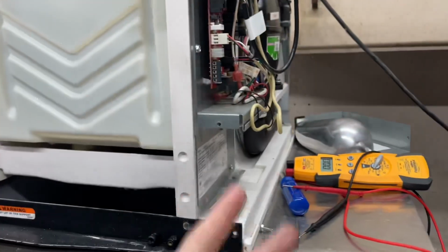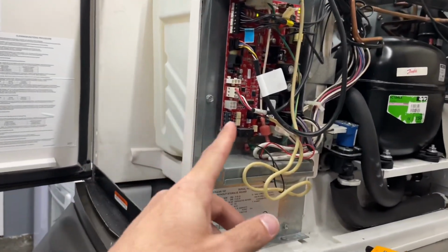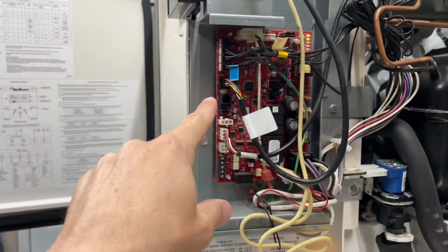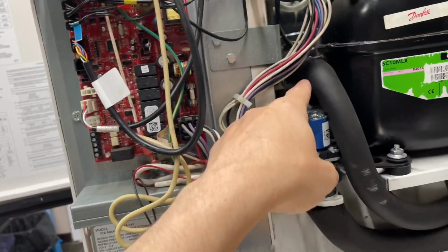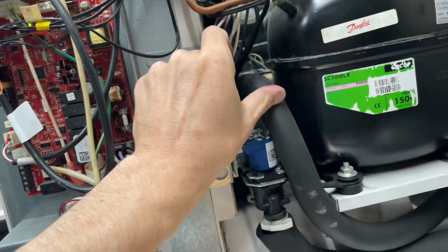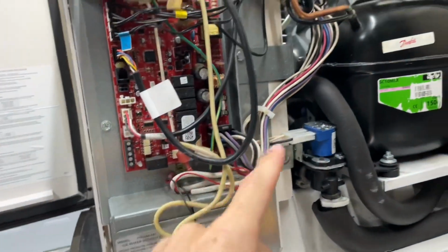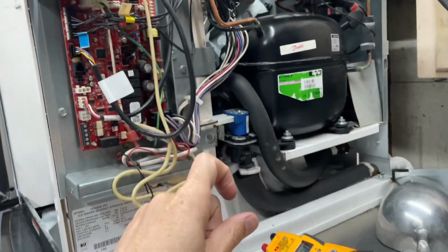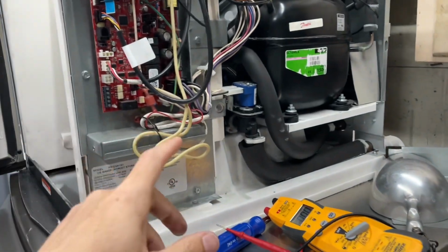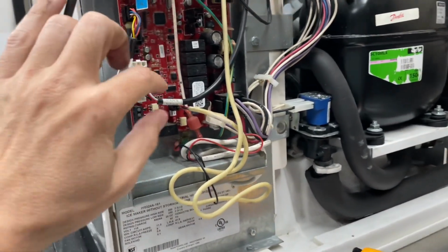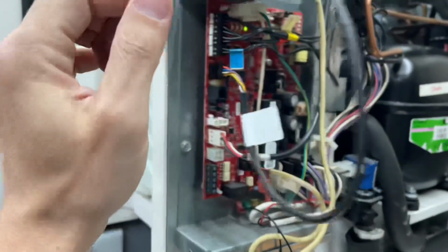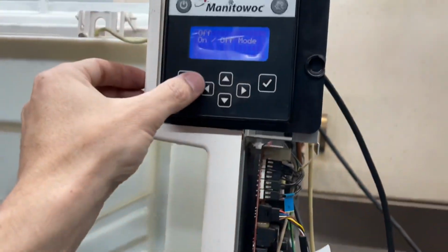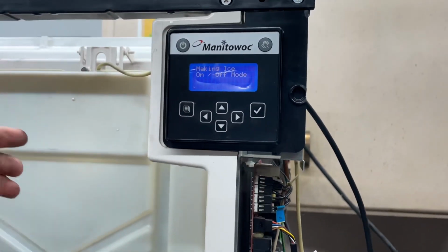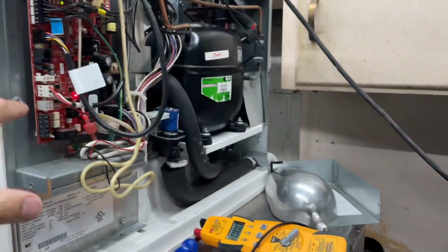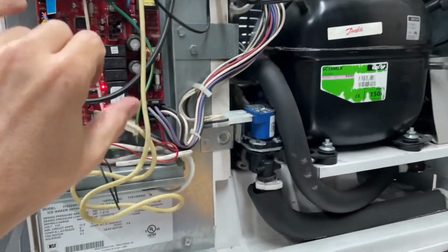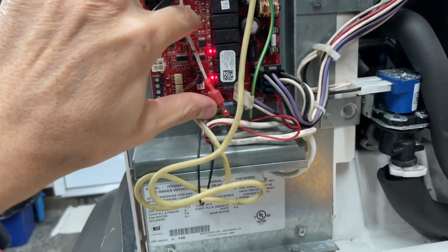That's step number 2. Step number 3, really easy as well, is you're going to want to make sure that this thing, the control board, is actually sending power to your water valve, which is right back here. Now, you could dig back there, unplug the water valve, and measure it at the valve, or make it easier on yourself and just check right here, the control board. What we're going to do is we are going to just turn this machine on, and then when the water valve energizes, I will show you where to measure.